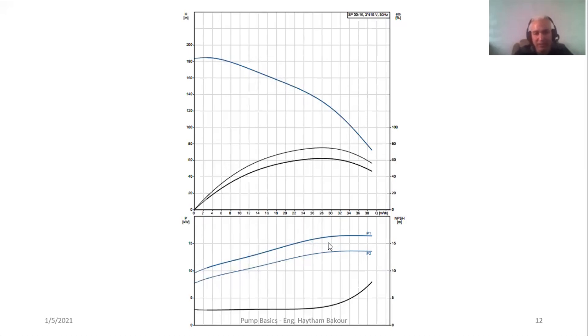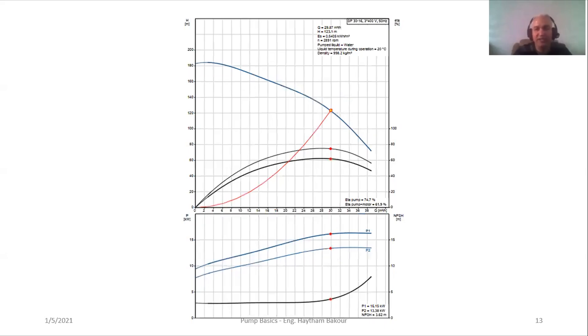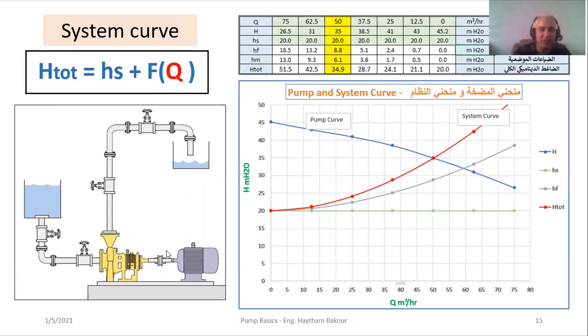On the chart we can see P1 in blue, which is the capacity of the engine or the pump, and the input in watts — this is the kilowatt for the pump. The manufacturing factory provides us with those charts. On the other hand, we have the system curve, which is related to the accessories and the system installed in real life — we have tanks, lines, valves, gates, and other accessories. To choose the perfect pump, we need to know the components of our system.